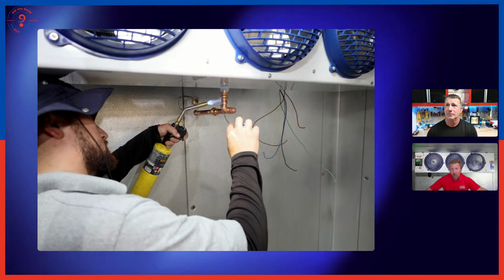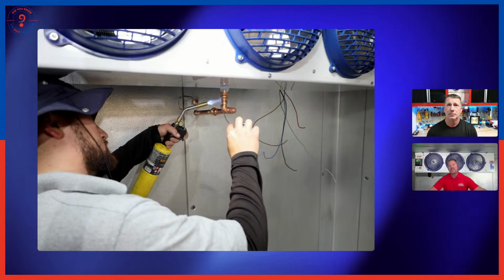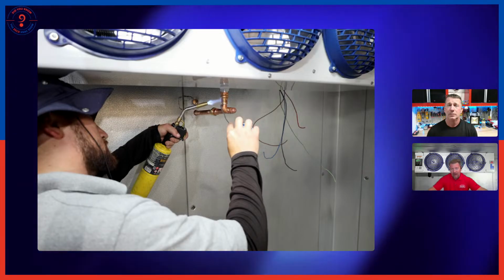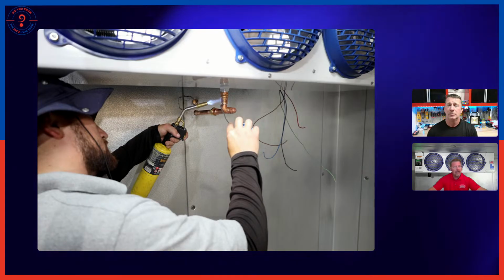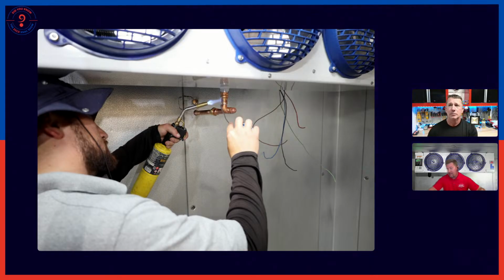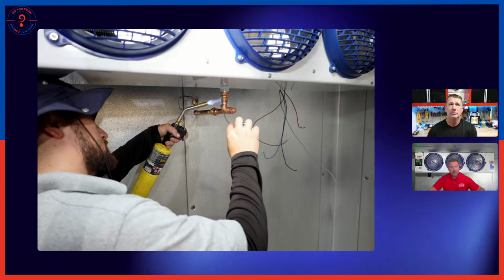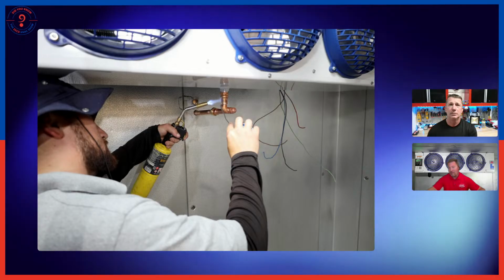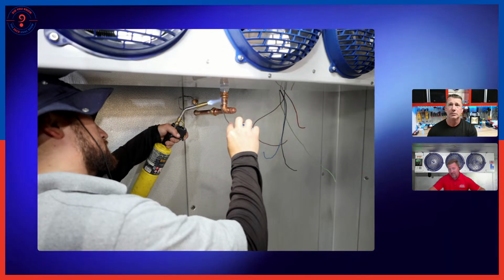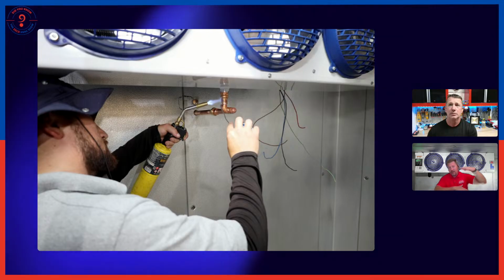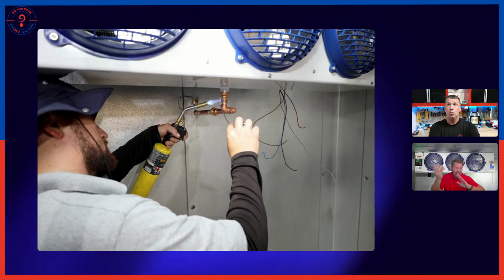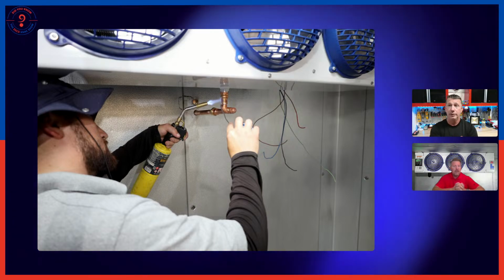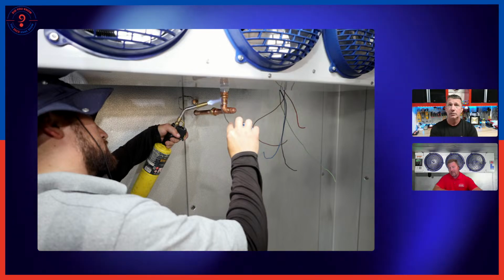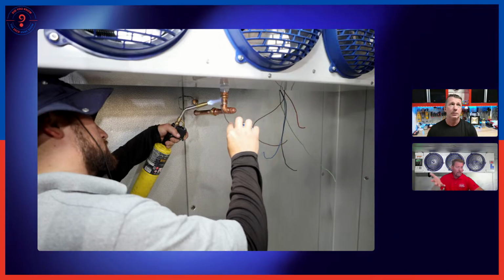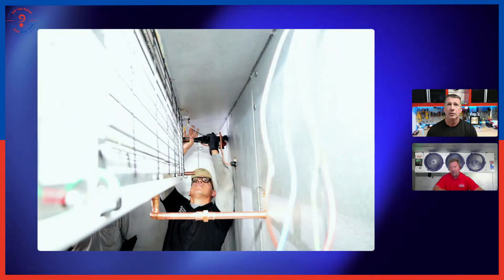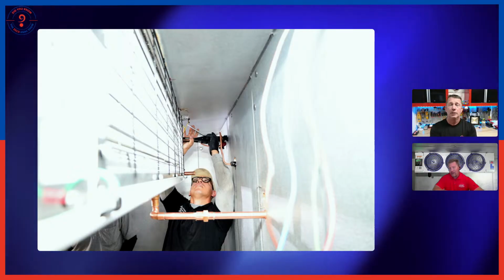One thing I do want to point out here, as we go through this, is something that I noted when I arrived on site and that is often overlooked: evaporator coil spacing. Heatcraft does have recommendations for that. Our recommendation, as long as I can remember, for these low profile style coils has been 1 1/3 times the height, which is 18 inches away from the wall. Now, when I arrived on this site, this coil was not mounted that far out. To no fault of the installers, they put the new coil exactly where the old coil was.